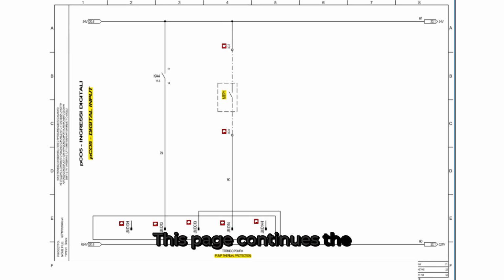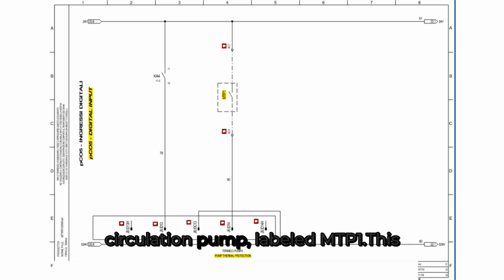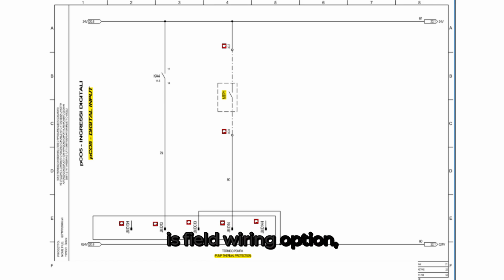This page continues the digital input section of the Carel PCO5 controller. The first vertical line represents a relay contact labeled KA4 for the circuit 2 high pressure switch. The second column represents the thermal protection feedback status for the evaporator or chilled water loop circulation pump, labeled MTP1. This is a field wiring option. If you wanted to control a pump installed external to the heat pump, the feedback status wire would be landed here. The terminal block is labeled as XC, and the terminal points are XC7 and XC8.